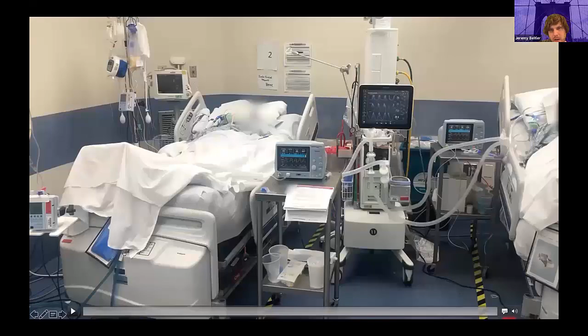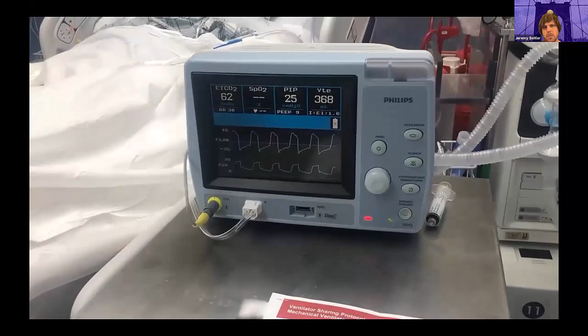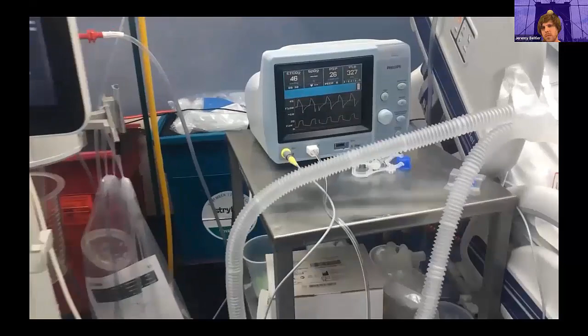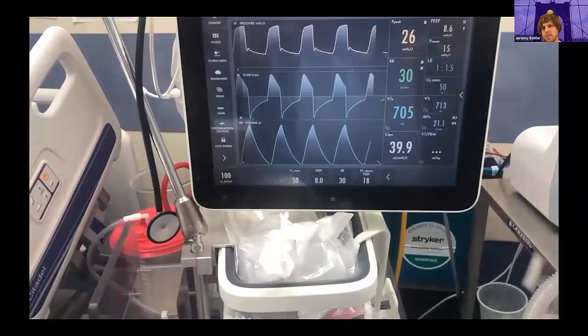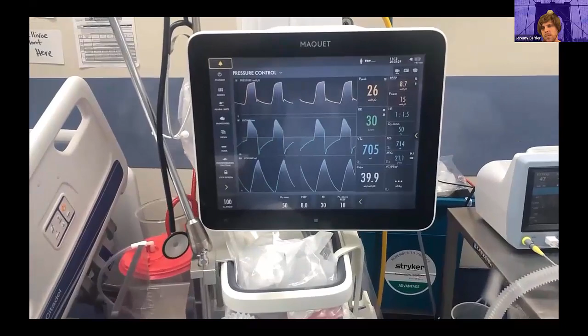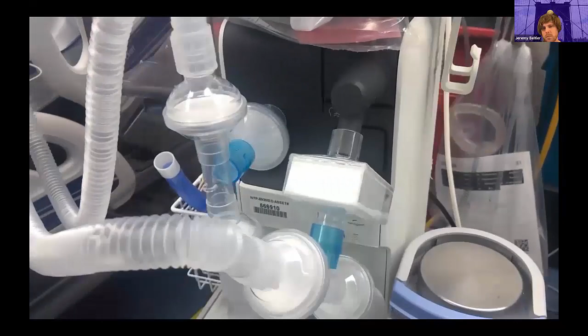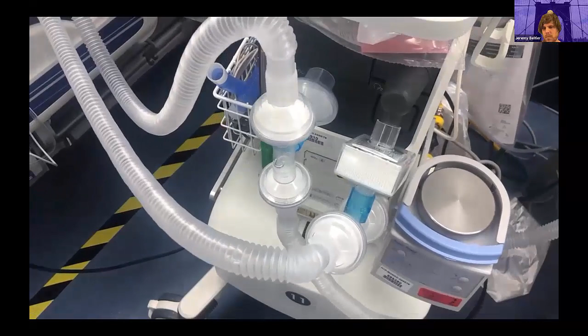This video shows 2 patients with COVID-19 associated ARDS being supported simultaneously with 1 ventilator, a strategy termed ventilator sharing. The patients are spaced roughly 8 feet apart with the ventilator and freestanding respiratory monitors between them. The patient-specific monitor is placed adjacent to each patient's bed, making clear to whom the values belong. These monitors display patient-specific tidal volume, flow, and airway pressure and associated waveforms. The ventilator, positioned in the middle, is set to the pressure control mode to ensure mechanical changes in one patient do not affect the other. Ventilator displayed tidal volumes indicate the combined value. The circuit configuration includes a T-adapter and redundant antimicrobial filters on the inspiratory and expiratory limbs. All supplies used are medical grade and intended for respiratory clinical care in mechanically ventilated patients.